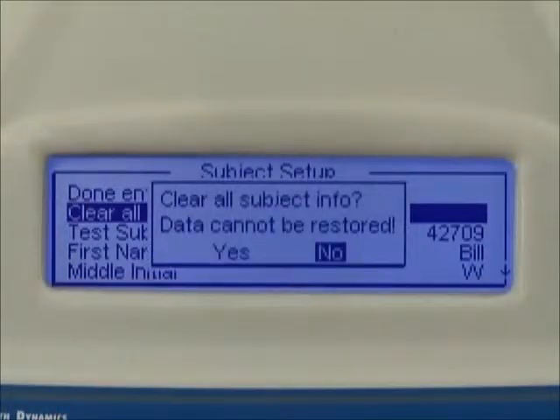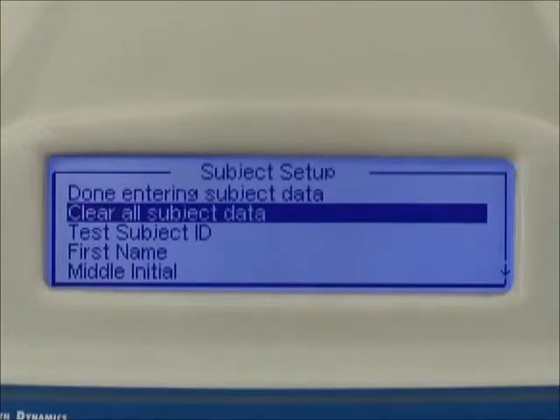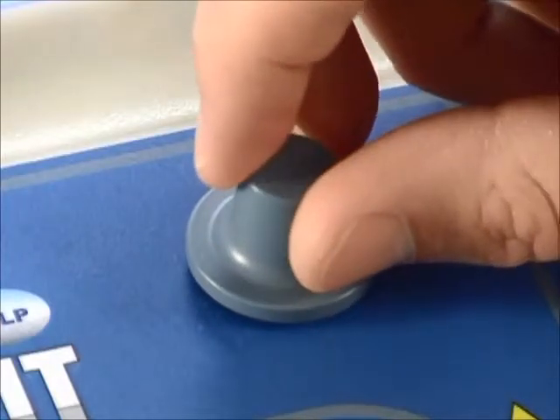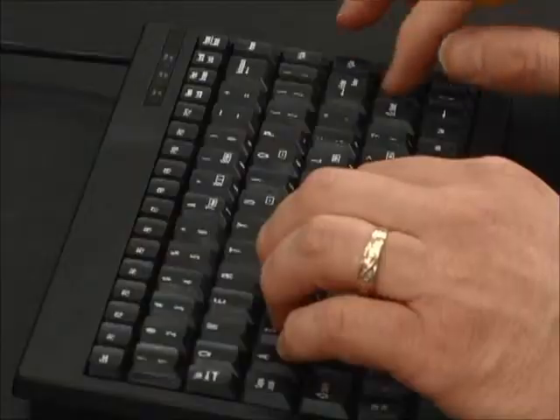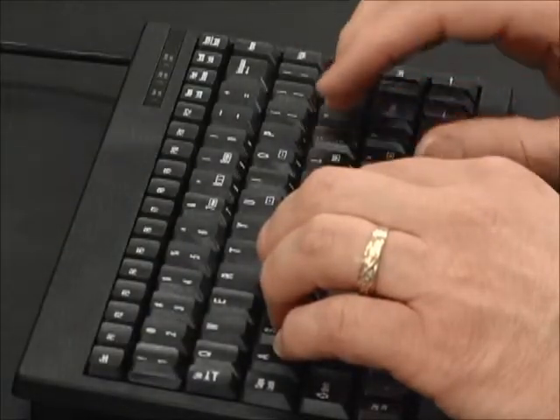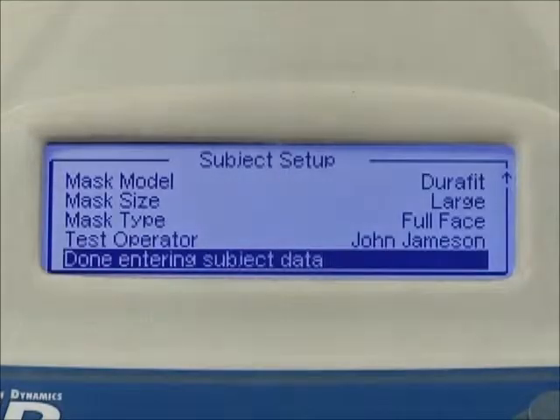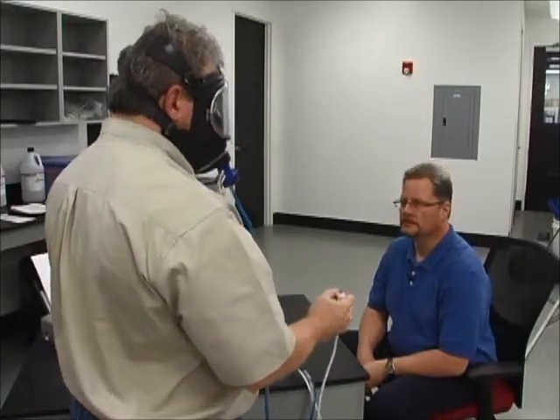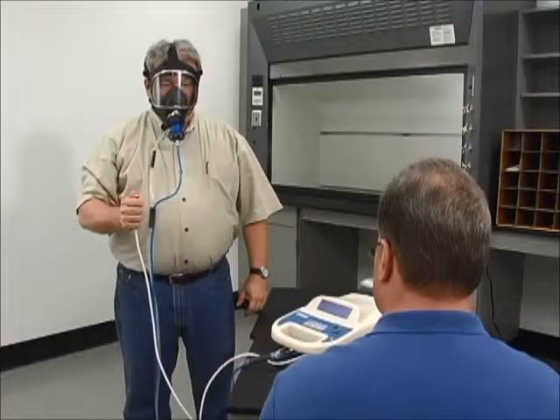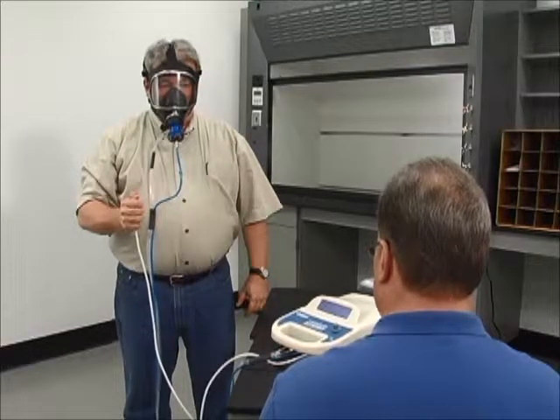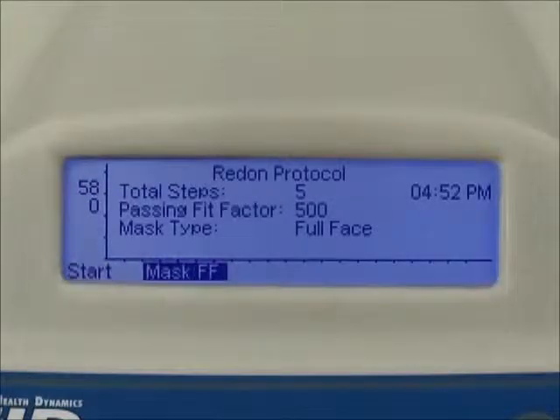If the keyboard is connected, you will be prompted to enter test information including ID number, name, mask size, and type. You can select Clear All Test Subject Data to clear all fields, or simply type over the existing information. To move to the next entry field, simply press the selector knob or the Enter key on the keyboard. After entering test operator name, you can then select Done Entering Subject Data. If there is no keyboard attached to the Quantifit, you will not be prompted for this personnel information. The operator would have to complete this information on the printout at the end of the test. When no keyboard is connected, the operator must choose between a half-face and full-face mask.